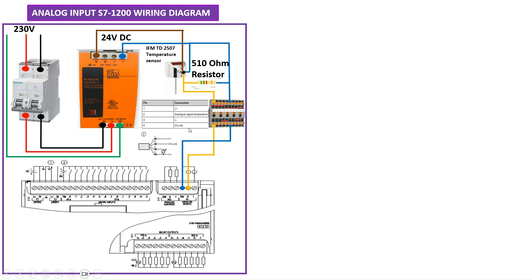The fourth pin is IO-Link, which we are not going to use here — in future videos I will explain how to use IO-Link connections. L+ is 24V DC which you connect to the sensor, and L− is 0V DC. The analog signal from the sensor on pin 2 you connect to the S7-1200 PLC analog input, and you also connect the negative of this voltage to the analog input terminals.